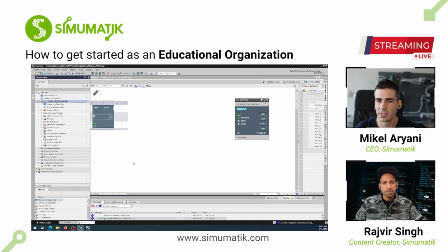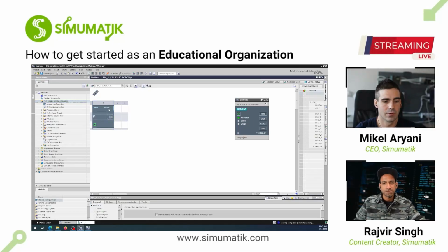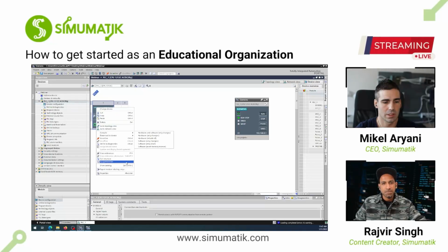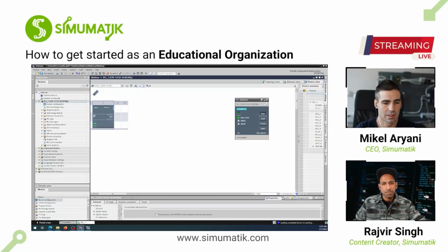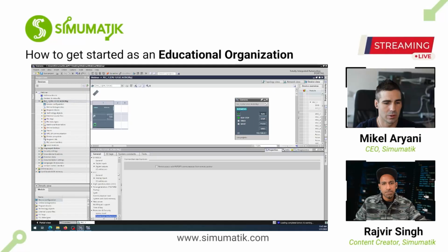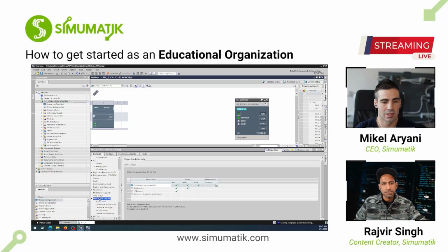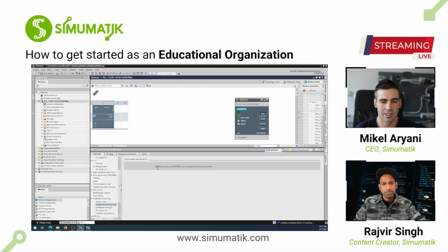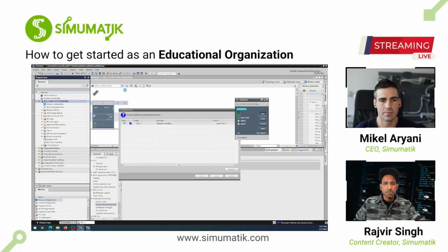And this is something we just need to do, and it's very quick. It's a few settings. First thing we need to do, just go here, properties, and let's expand this. We need to go to communication, and here in the protection and security, make sure you have full access, and then here you activate PUT/GET. Once we do that, save and download this to the PLC.